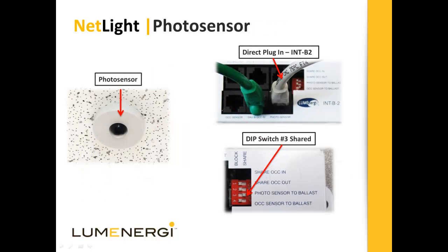Photosensors are ceiling mounted. The sensor connects into the interconnect box photosensor port and requires dip switch number 3 to be set to share. The ceiling plan may not display the best physical location of the sensor. In some cases, designers simply place the sensor in a general location on the plan and put a descriptive note in the legend indicating placement should be decided during installation.